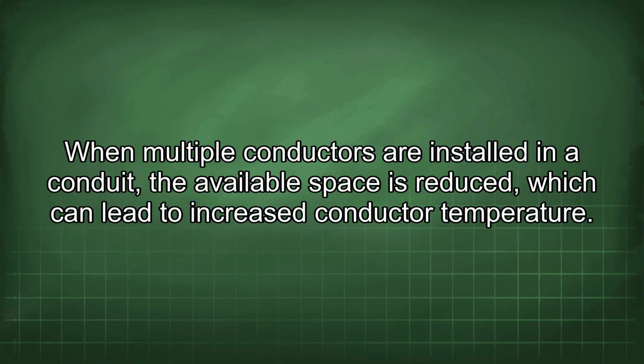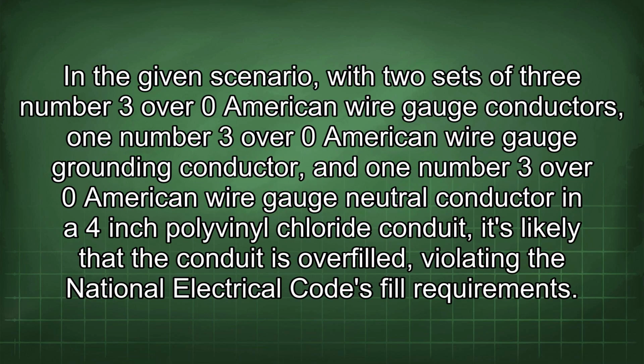When multiple conductors are installed in a conduit, the available space is reduced, which can lead to increased conductor temperature. In the given scenario, with two sets of 3 number 3/0 American wire gauge conductors, one number 3/0 American wire gauge grounding conductor, and one number 3/0 American wire gauge neutral conductor in a 4-inch polyvinyl chloride conduit, it's likely that the conduit is overfilled, violating the National Electrical Code's fill requirements.